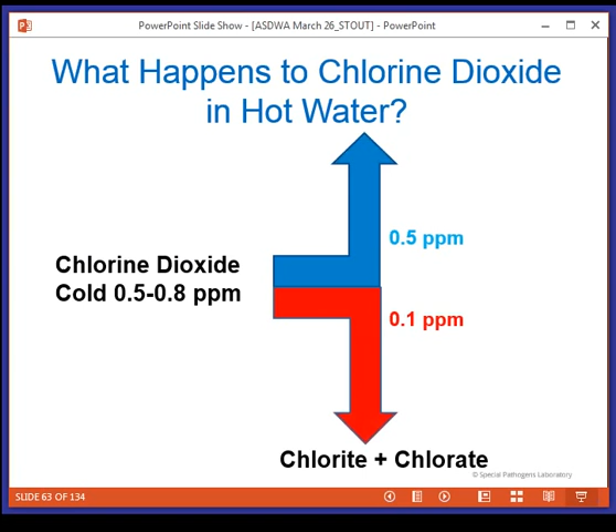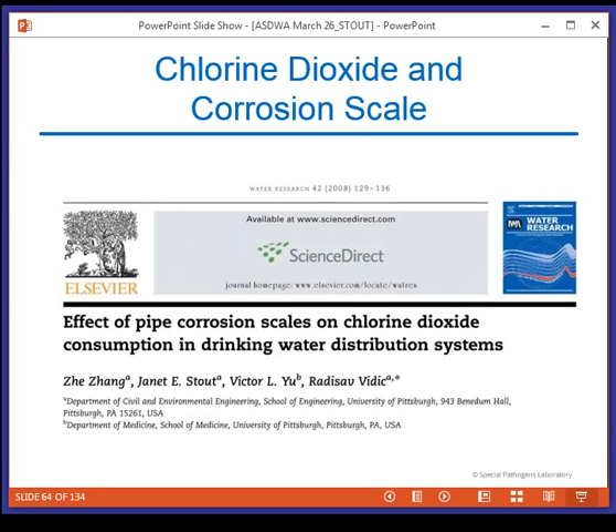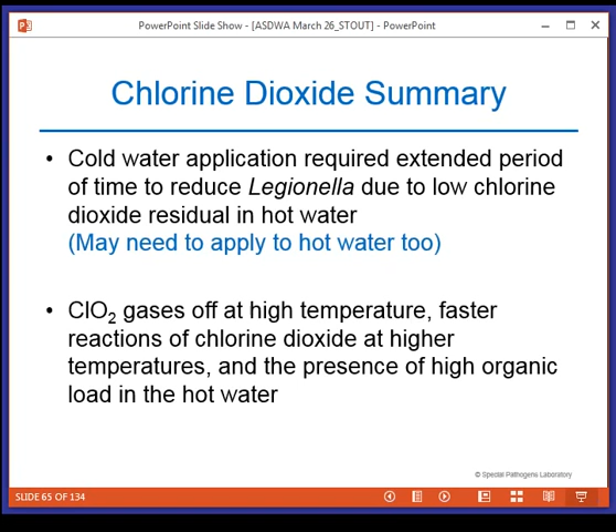We also learned that the presence of corrosion scale negatively impacts the efficacy of chlorine dioxide. This was published in 2008 in Water Research by one of our graduate students at the University of Pittsburgh. So another thing to be aware of: if there's galvanized pipe, chlorine dioxide may have a problem. Again, with cold water application, an extended period of time is necessary to have the desired effect. You may want to add chlorine dioxide directly to the hot water to get a more rapid response. It gases off at high temperature and reacts very quickly, particularly in the presence of high organic load and scale and disinfection byproducts.